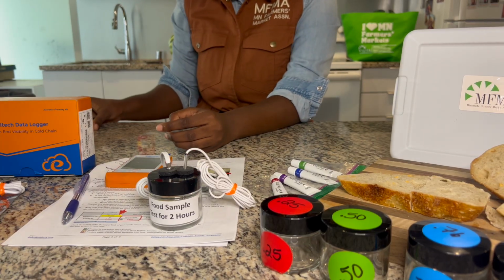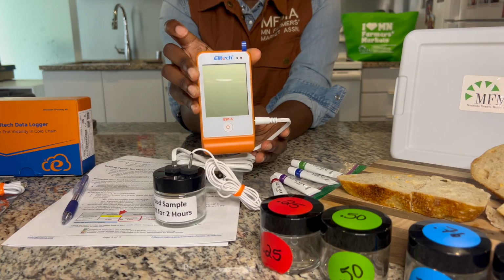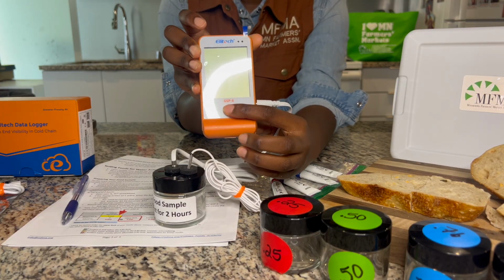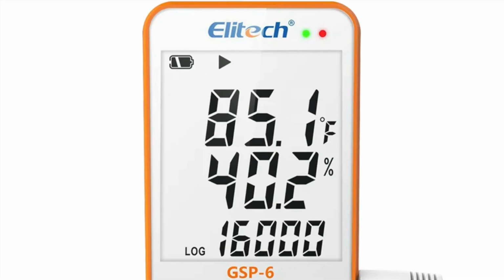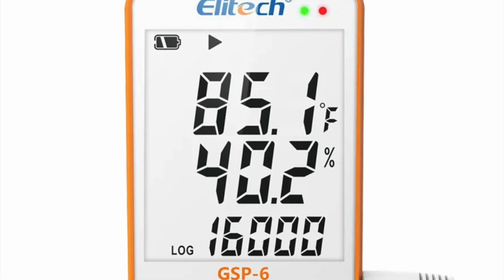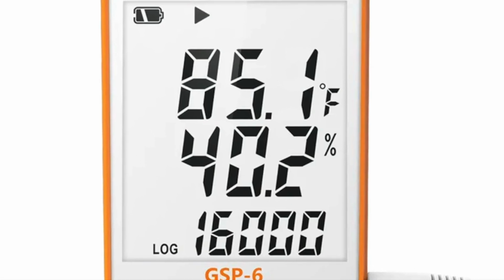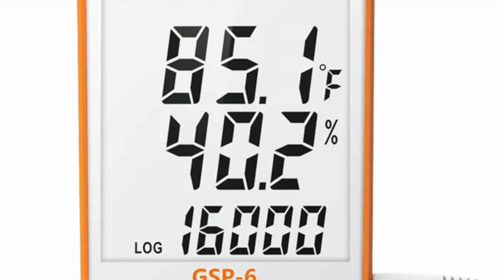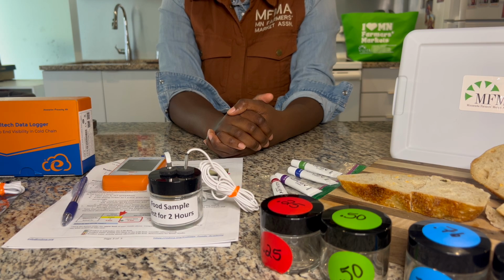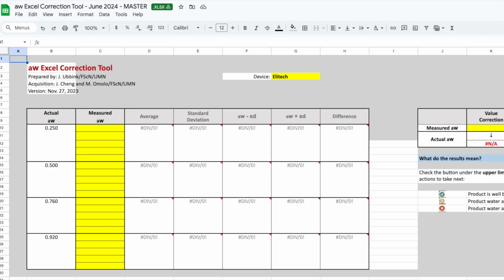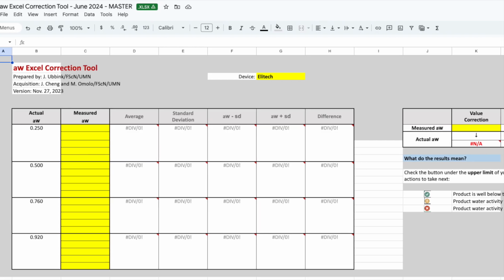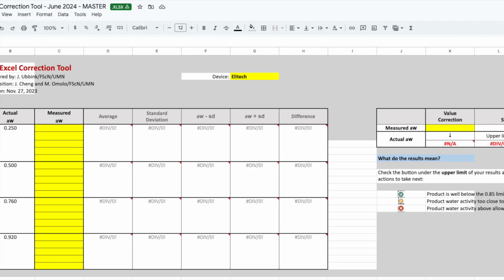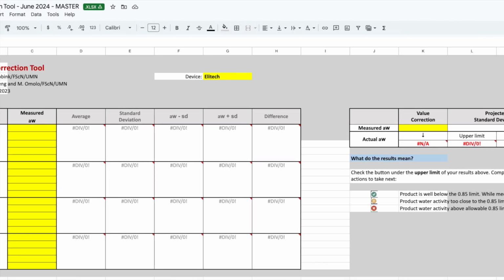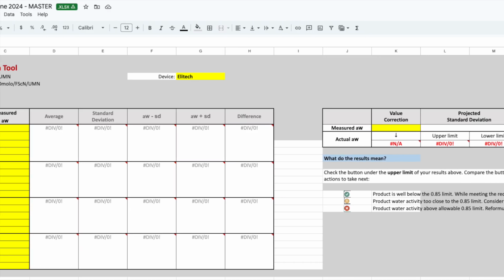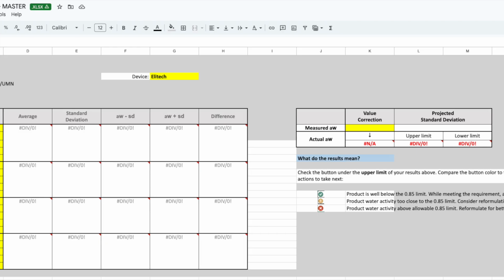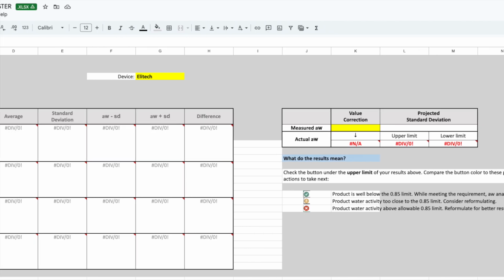After 2 hours, step 1, press the button on the GSP-6 to read the middle number on the display screen. Step 2, convert the percentage to a decimal by moving the decimal 2 places to the left. Write this number down. Step 3, repeat this test 2 more times over 6 hours total. Step 4, add the 3 numbers, then divide by 3 to get the average. Step 5, enter the average number into the AWECT spreadsheet. The AWECT spreadsheet will apply the correction factor based on the calibration and display an adjusted water activity value.